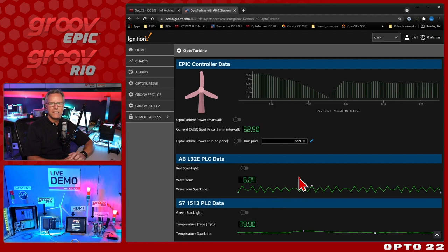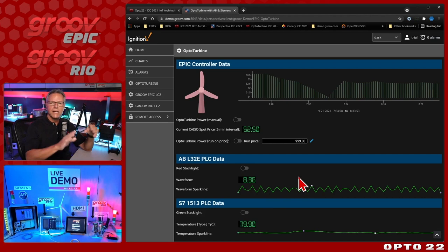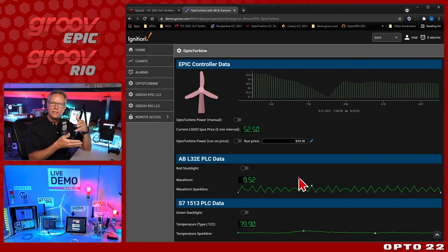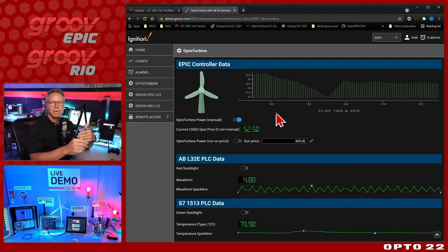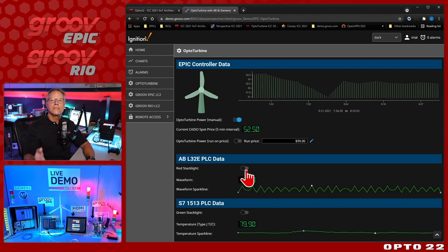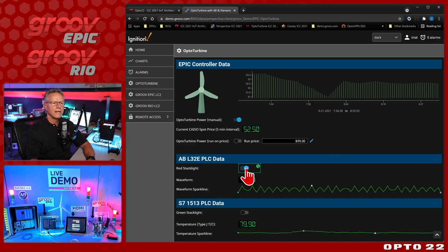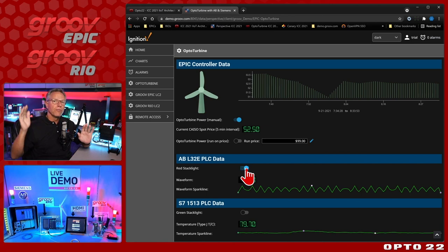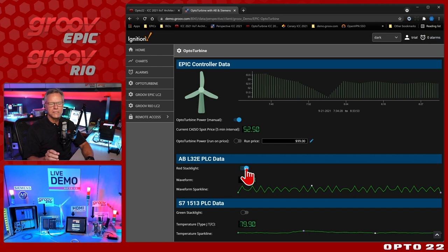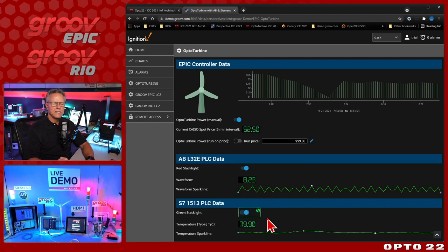Now on the SCADA side, I'm subscribed to that data and seeing everything in there. You also may remember that when I mentioned connecting from the edge up to the broker, I persist that connection. This allows data to flow back out to the edge. So for example, maybe I want to start my turbine. I'll go ahead and click this button and there you go. You can see in the screen down below I've actually initiated a command from the main SCADA to turn on the turbine. I can also talk to the PLCs in the OT protected zone - I may want to turn on my red stack light. There you see it come on. The other thing that should be evident is the performance. You see how fast I make an action and it actually occurs all the way out on the edge through the broker, all encrypted, all authenticated. You're not giving up performance to implement these cybersecurity features. We'll also turn on the Siemens green light. Works very, very well.